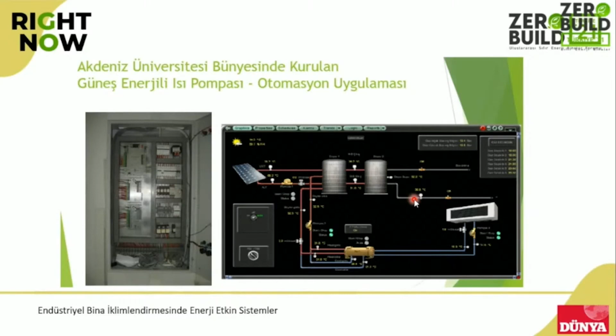Heat pumps become also important as we target zero energy buildings. They should be supported by renewable energy resources like sun. At Akdeniz University, we used this pump with solar support, with monitoring through the SCADA system and a PLC, trying to operate it in the most efficient sense. We saw that the system can increase up to 4 COP and work at an average of 2.93.